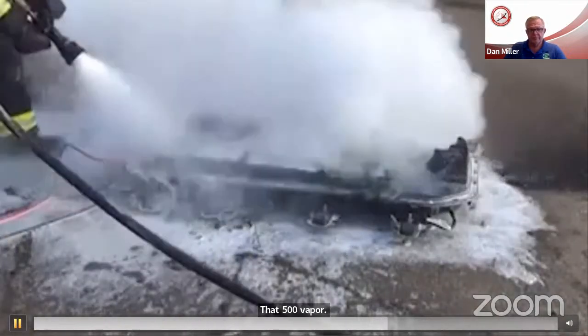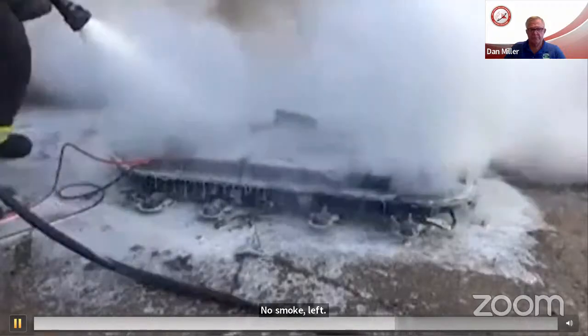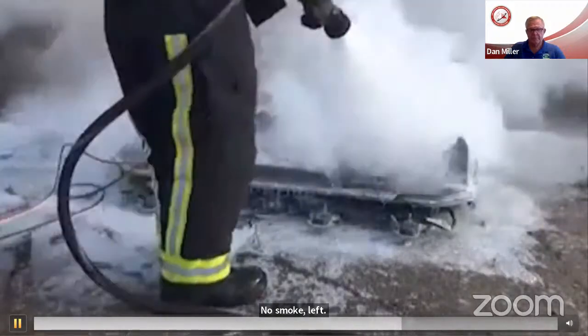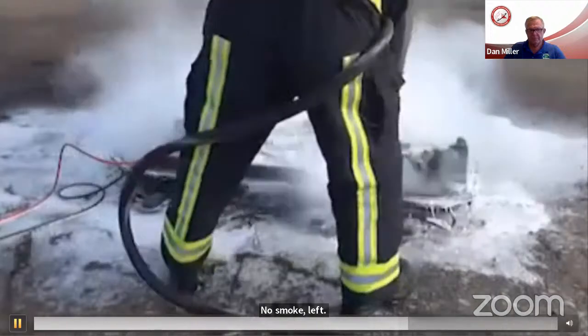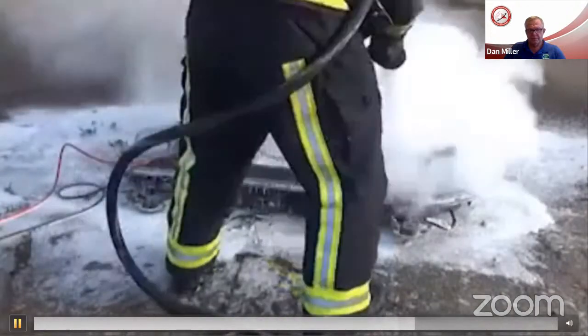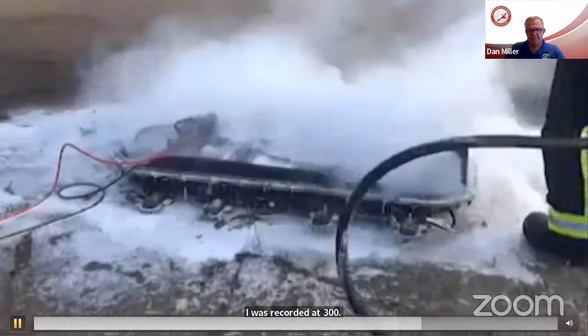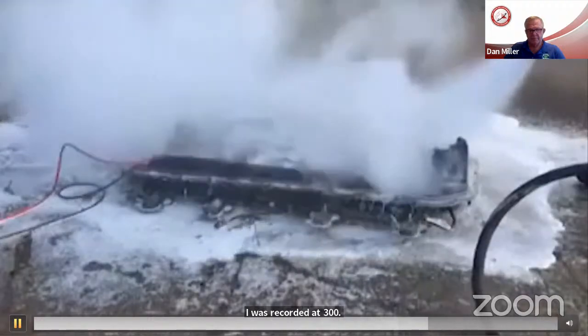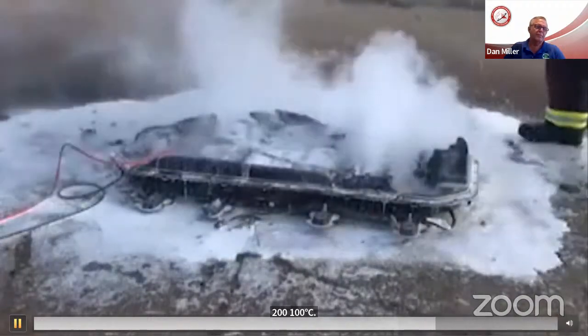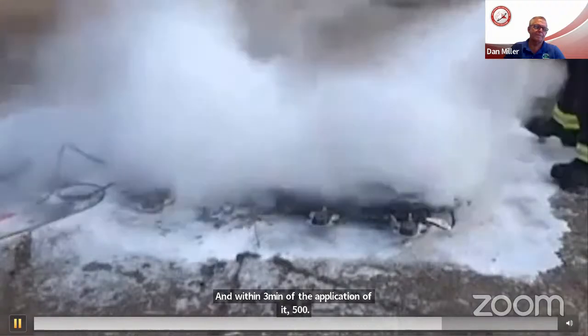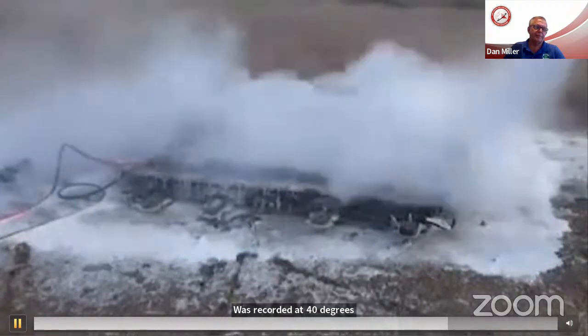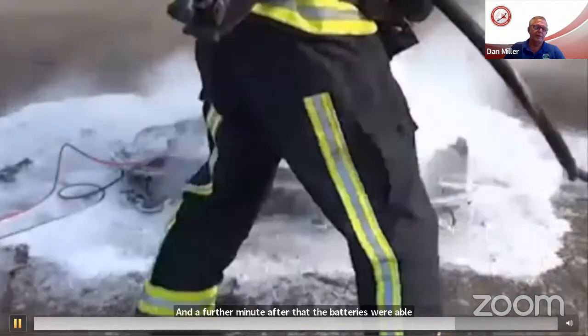The temperature very quickly drops down from over 400 degrees Celsius and was recorded at 300, 200, 100 degrees Celsius, and within 3 minutes of the application of F500 was recorded at 40 degrees Celsius. A further minute after that, the batteries were able to be handled.